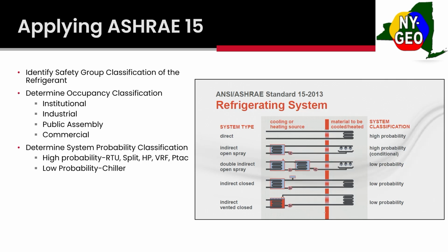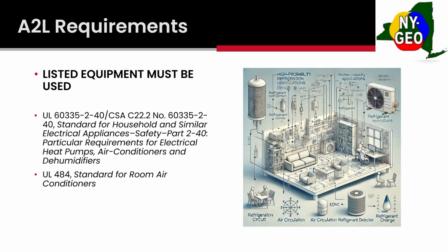So A2L. When you first start around the A2L, before you do anything, before you pass go, before you collect $200, you need to make sure your equipment is UL listed, UL 60335-2-40. This pretty much means it meets all the new A2L regulations with the sensors, sparkless motors, stuff like that. So that is step one before you do anything with your design. Make sure you're using the right equipment. That's really important.